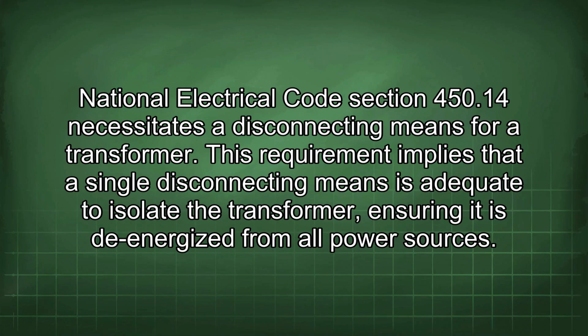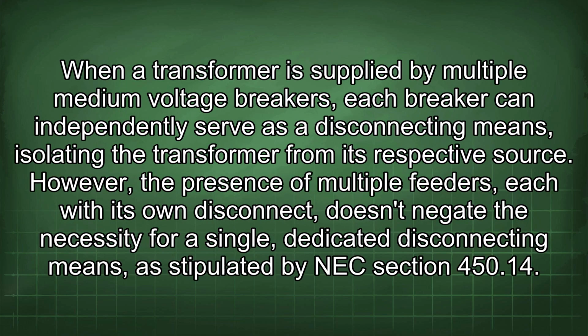National Electrical Code Section 450.14 necessitates a disconnecting means for a transformer. This requirement implies that a single disconnecting means is adequate to isolate the transformer, ensuring it is de-energized from all power sources. When a transformer is supplied by multiple medium voltage breakers, each breaker can independently serve as a disconnecting means, isolating the transformer from its respective source.